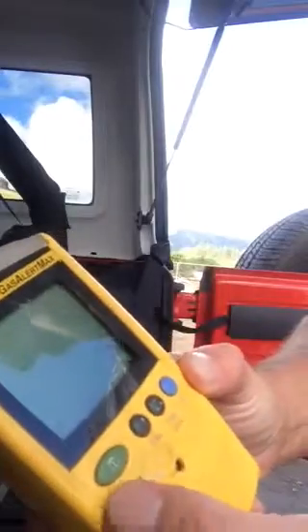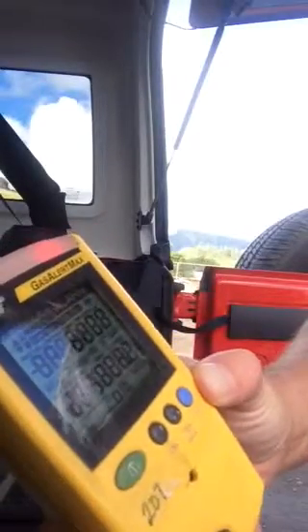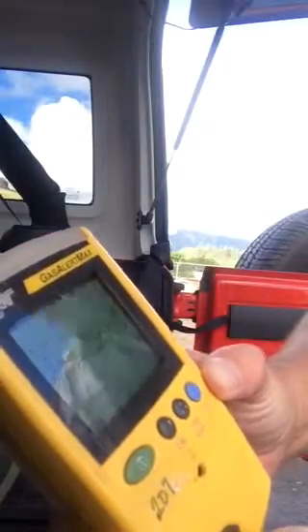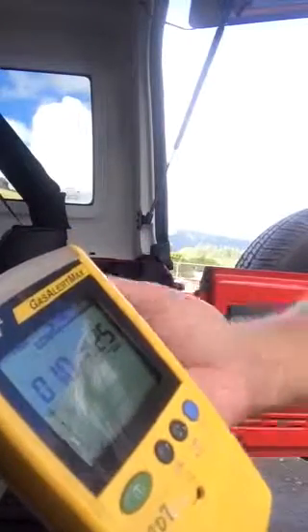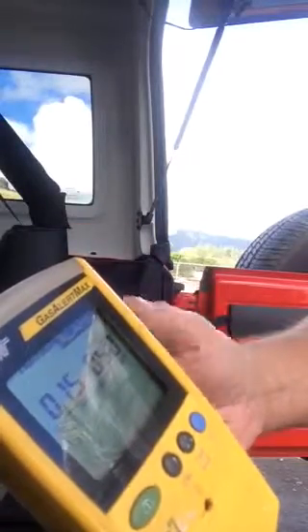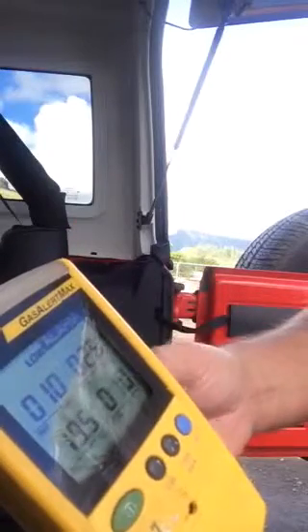Alright, to do the calibration on these, first things first is turn it on. It's going to go through its little startup sequence. Listen to the pump. Make sure it isn't making any odd sounds like grinding or it's varying in speed or anything like that. If that's the case, then it's probably going to need to be replaced.